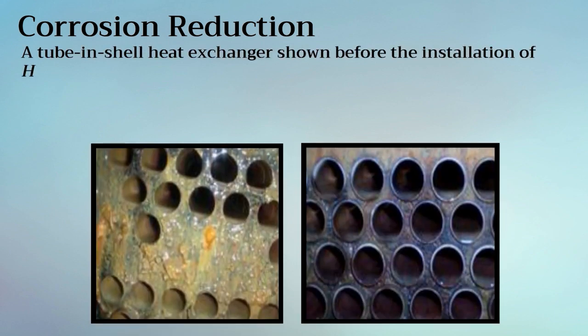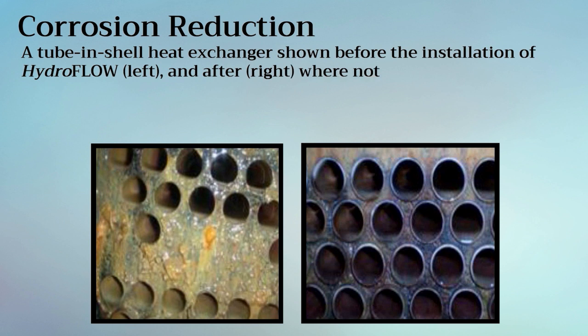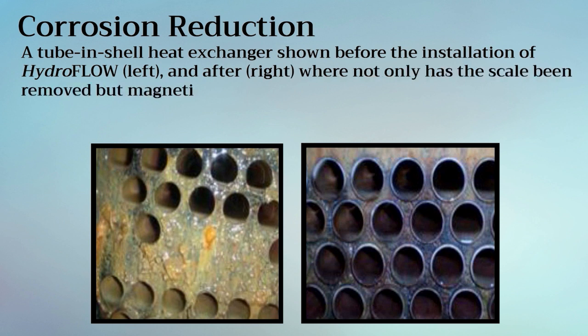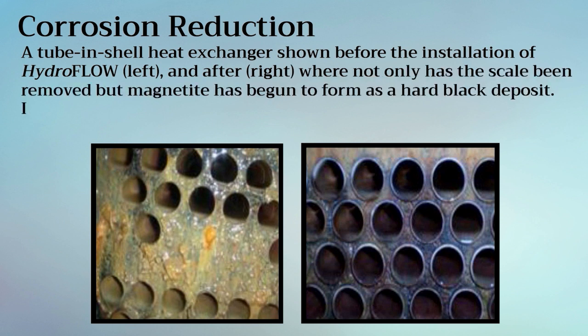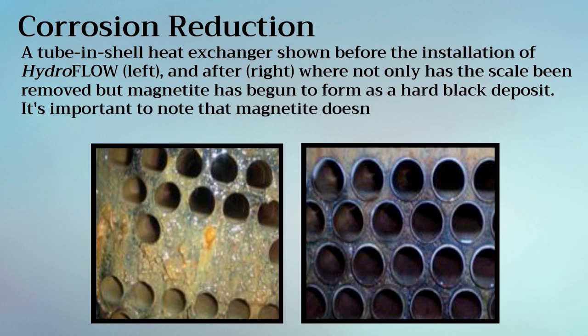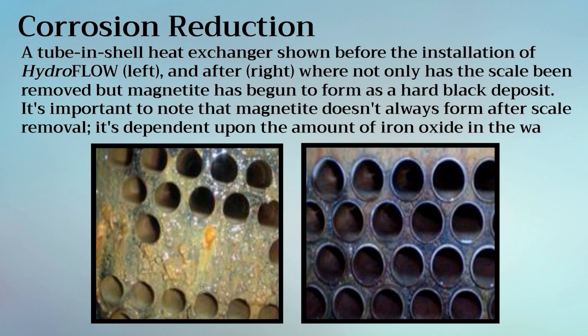A tube and shell heat exchanger, shown before the installation of HydroFLOW on the left and after on the right, where not only has the scale been removed, but magnetite has begun to form as a hard black deposit. It's important to note that magnetite doesn't always form after scale removal. It's dependent upon the amount of iron oxide in the water.